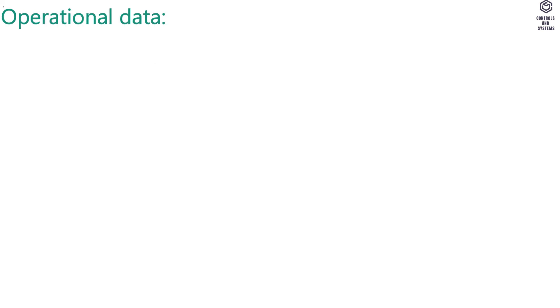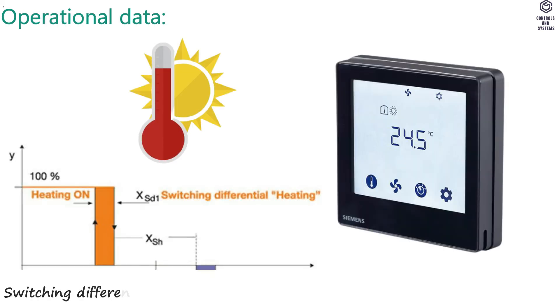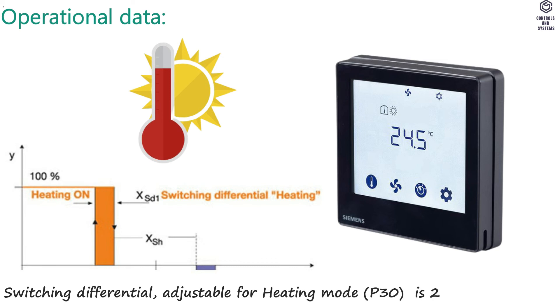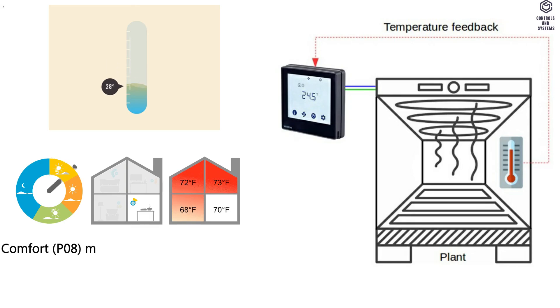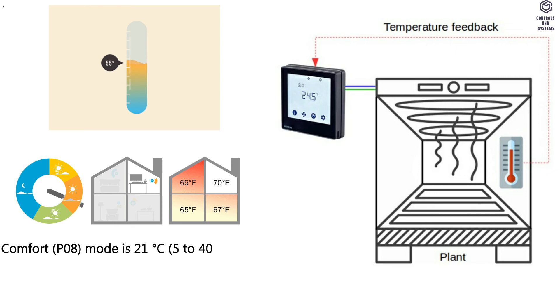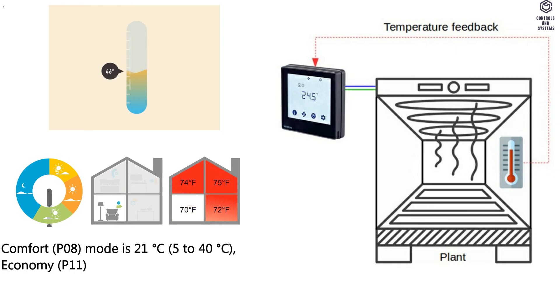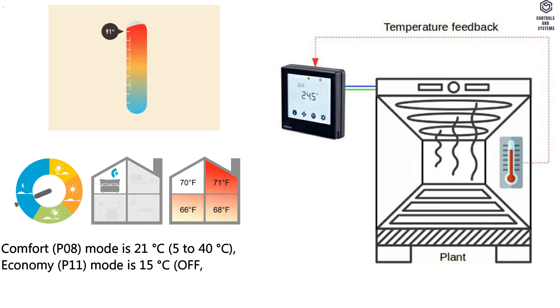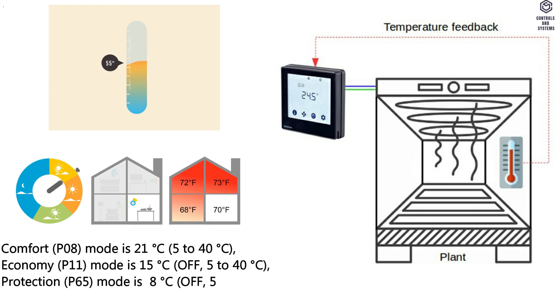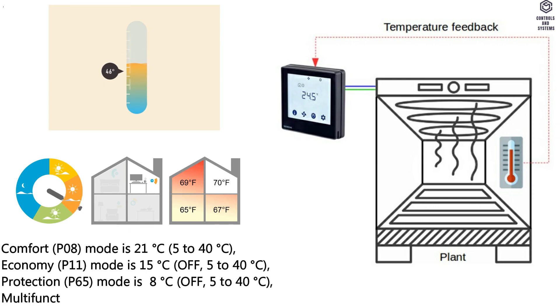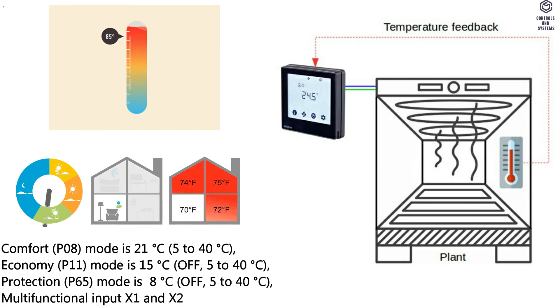Operational Data. Switching differential — adjustable for heating mode P30: 2K, range 0.5 to 6K. Set point setting and range: comfort mode default 21°C, range 5 to 40°C; economy mode default 15°C, range 5 to 40°C (or off); protection mode default 8°C, range 5 to 40°C (or off).